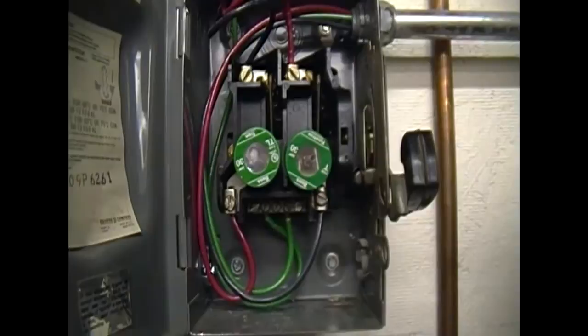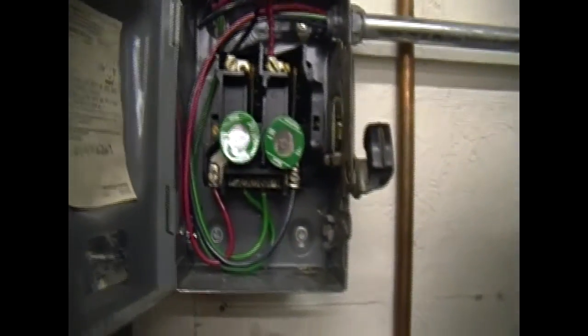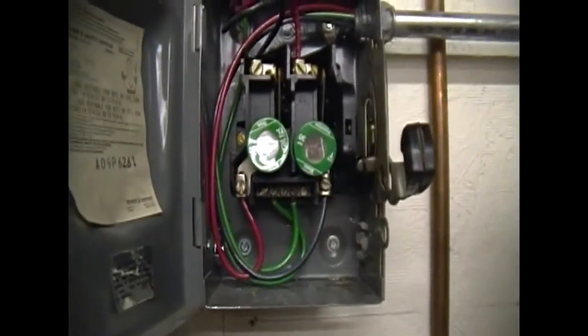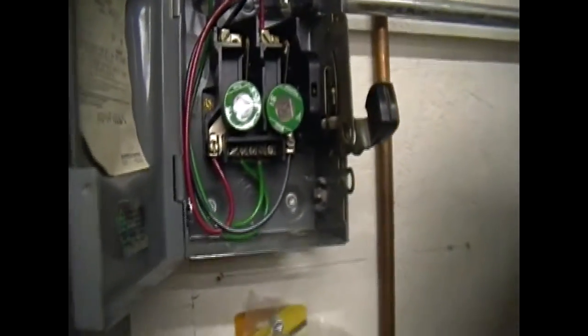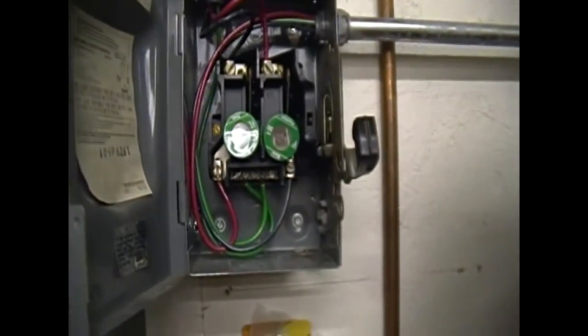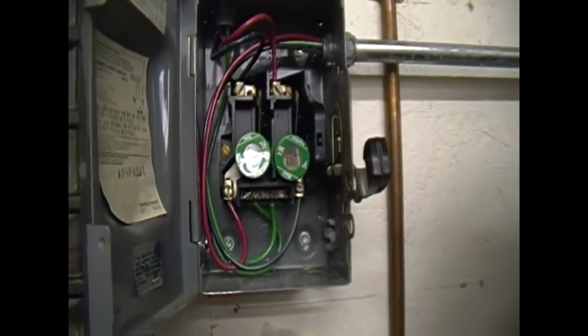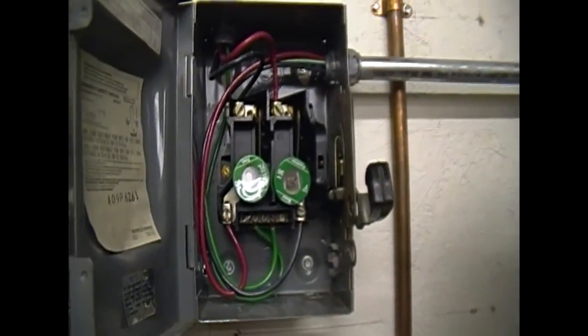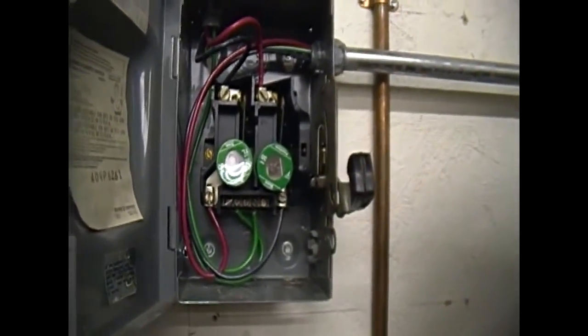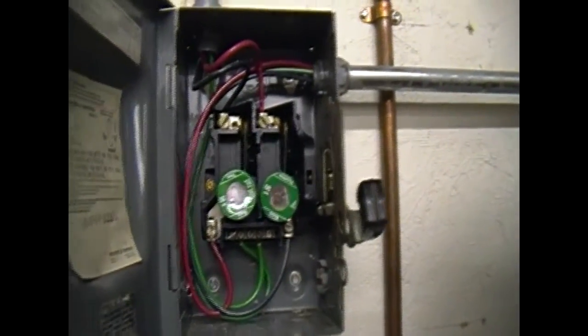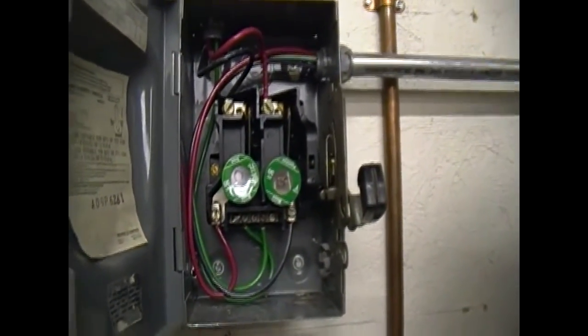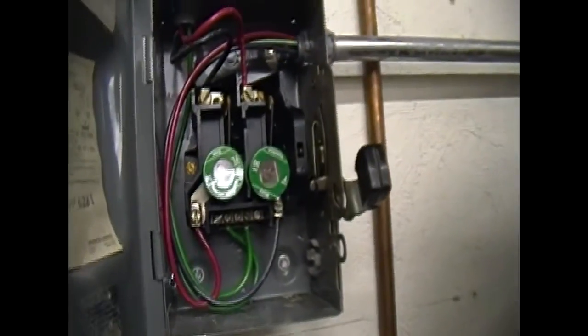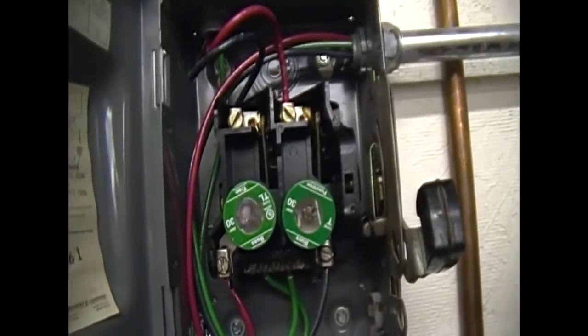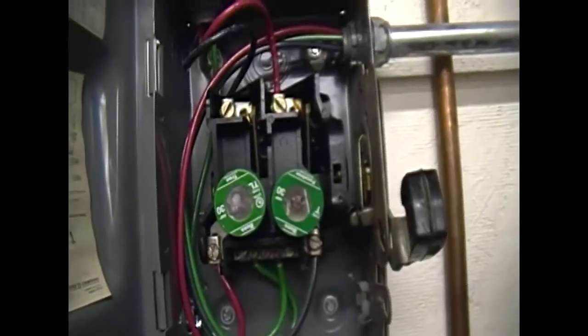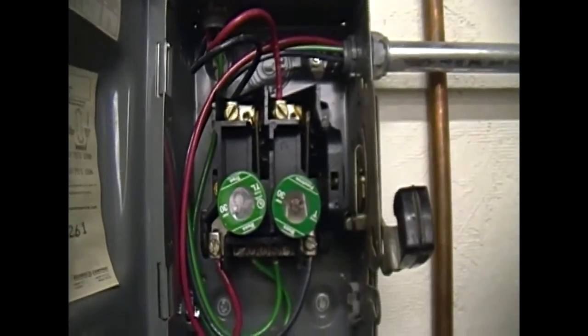And the circuit breaker over in the circuit breaker panel box is actually new when I did this project, because I had to pull heavier gauge wire. This is a 10 gauge wire, and so from a 20 amp breaker to a 30, which is sized perfectly for this application. It's a 25 amp load or a 24 amp load, number 10 gauge wire. So for whatever reason, this particular fuse is always blowing. So I'm going to replace it again.